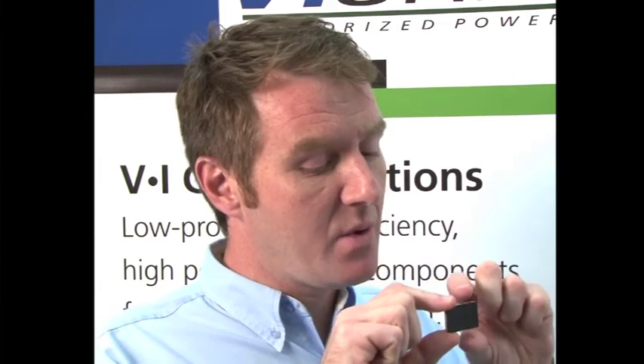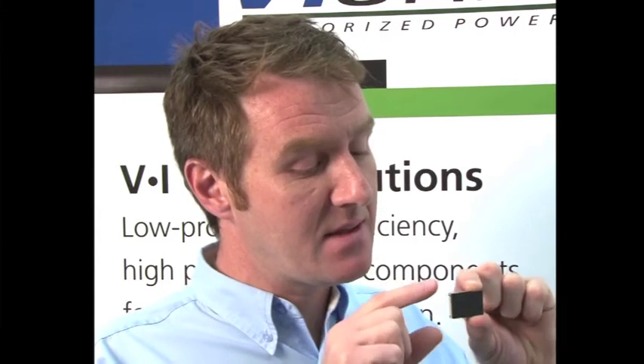In addition, a traditional power supply would normally have a large bank of capacitors for a good transient response. With the voltage transformation module, this is a very low impedance device, less than 1 milliohm from DC up to a megahertz. This means that when the load wakes up and demands to pull power from that bulk capacitance, it can see through the transformer to the higher voltage rail.